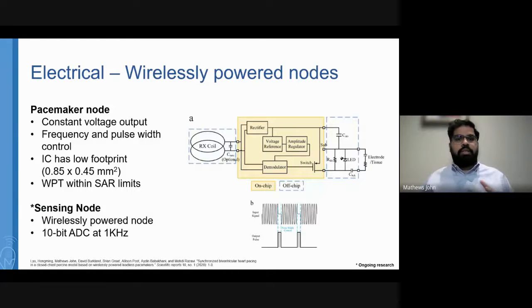Going into each of the subsystems for the wirelessly powered pacemaker: the electrical subsystem has a couple of features, the major one being the pacemaker node. This earlier version of the node has a constant voltage output, where the frequency and pulse width can be controlled by modulating the radio frequency going into the node. This IC has an extremely low footprint, about 0.85 by 0.45 millimeters square, and wireless power transfer has been shown to be within the SAR, or specific absorption rate limits, set by the IEEE.